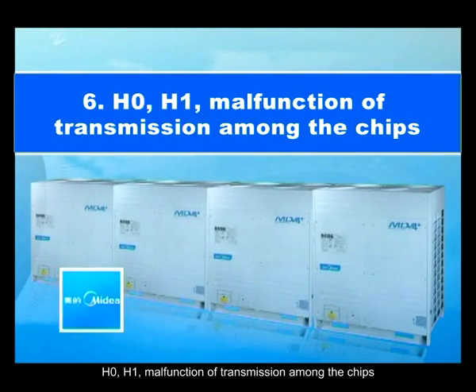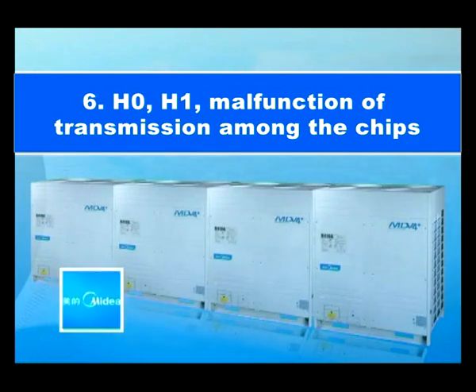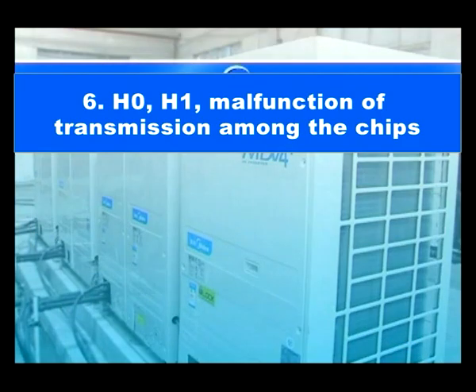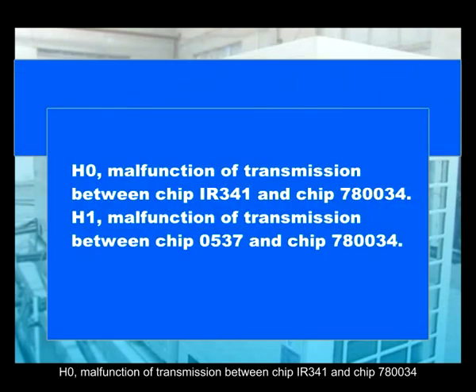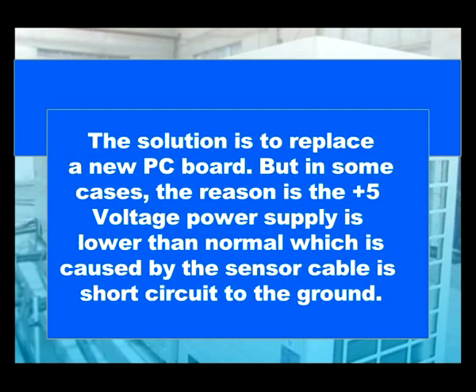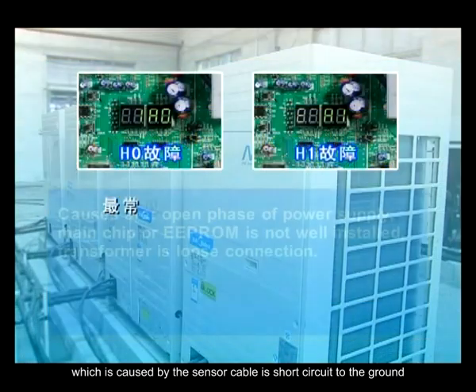H0, H1, malfunction of transmission among the chips. H0, malfunction of transmission between the chip IR341 and chip 780034. H1, malfunction of transmission between chip 0537 and chip 780034. The solution is to replace a new PC board. But in some cases, the reason is the +5 volt power supply is lower than normal, which is caused by the sensor cable short circuit to the ground.